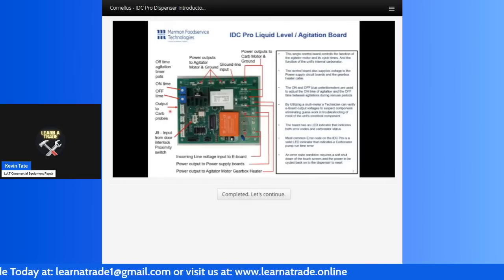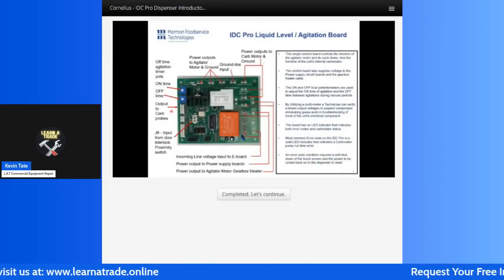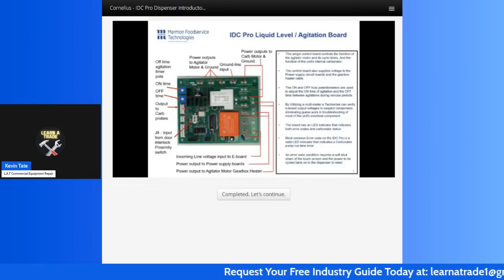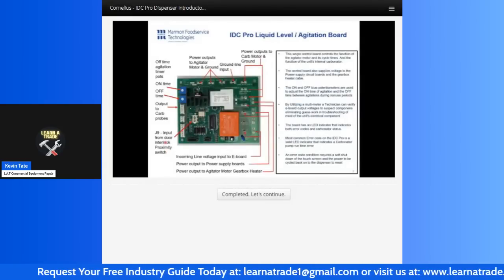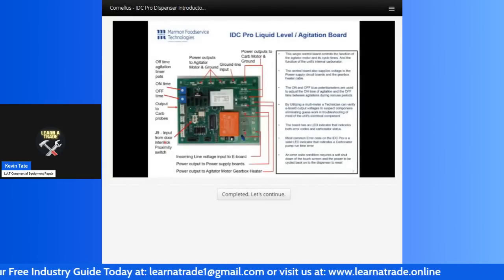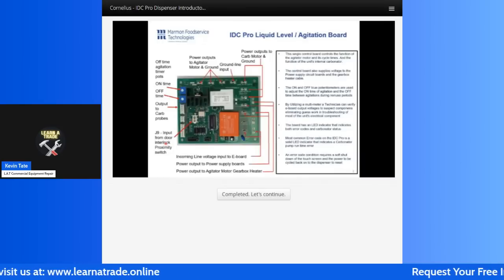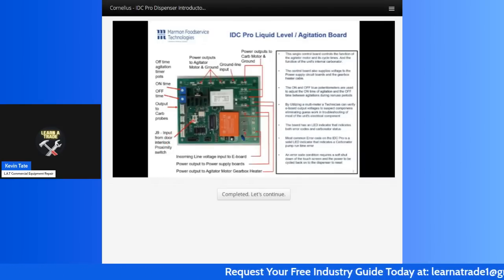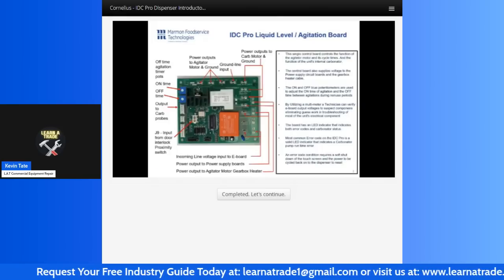Then there's also the high and the low carbonator probes for the carbonator tank. And that harnessing for those two probes is plugged into the board at this location right here. And then we've got the interlock switch or the reed switch that tells whether the front door of the display is open or the lid on the hopper is off. And of course, if that switch isn't satisfied, be it the door open or the lid on the ice bin off, the board sees that and it will not allow the agitator motor to power up and run. So we'll go to the next slide.